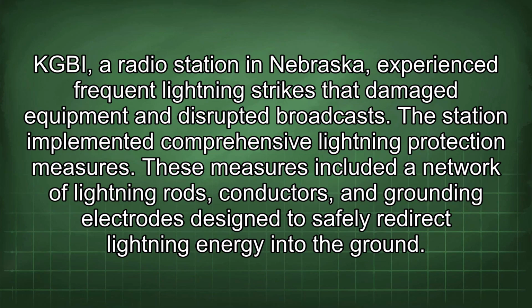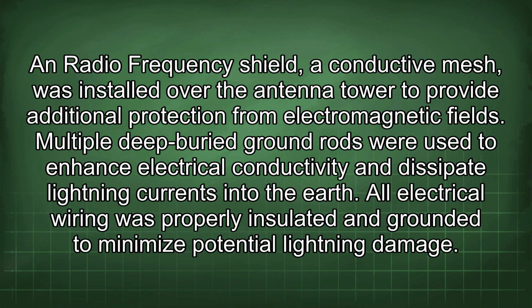KGBI, a radio station in Nebraska, experienced frequent lightning strikes that damaged equipment and disrupted broadcasts. The station implemented comprehensive lightning protection measures. These measures included a network of lightning rods, conductors, and grounding electrodes designed to safely redirect lightning energy into the ground. A radio frequency shield, a conductive mesh, was installed over the antenna tower to provide additional protection from electromagnetic fields. Multiple deep-buried ground rods were used to enhance electrical conductivity and dissipate lightning currents into the earth.